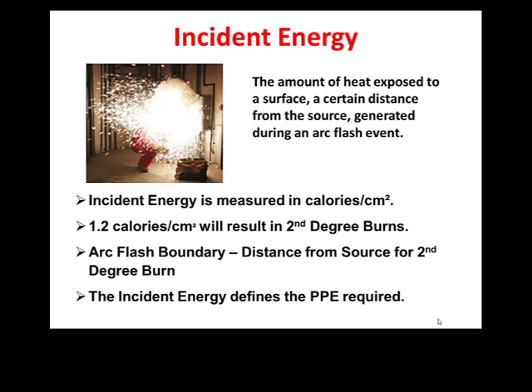The amount of energy or heat generated from an arc flash is referred to as incident energy and is measured in calories per square centimeter. Holding a cigarette lighter to the tip of your finger for 1 second equals 1 calorie per square centimeter. 1.2 calories per square centimeter will result in a second-degree burn. The arc flash boundary is the distance from the source of the arc where a second-degree burn can occur. The available incident energy determines what PPE is required to prevent a second-degree burn if exposed to an arc flash.